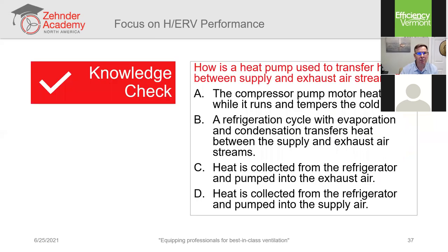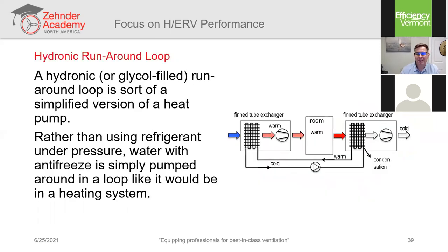The hydronic runaround loop is much less common but does exist. It's not much different from a vapor compression cycle, except you're not compressing vapor — you're pumping water through two separate coils in two different plenums, collecting energy from one and delivering it to the other airstream.